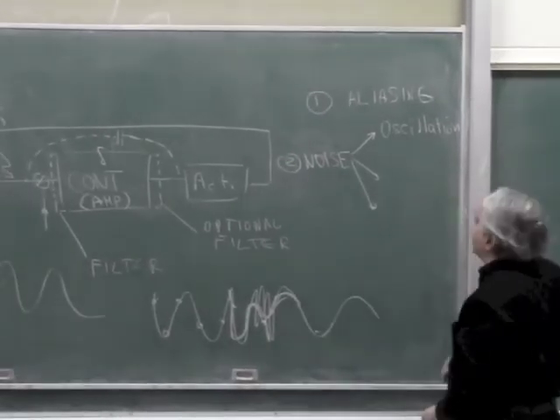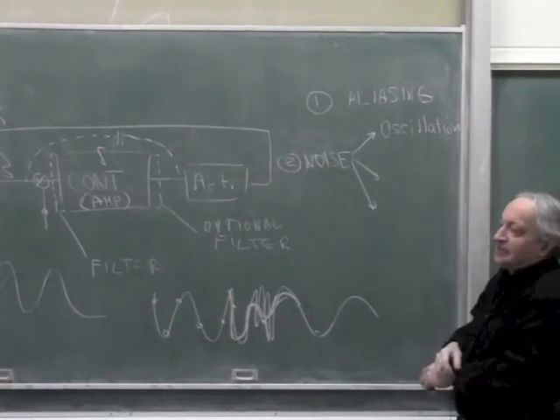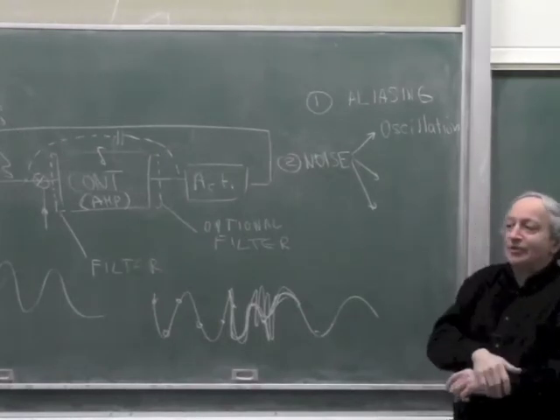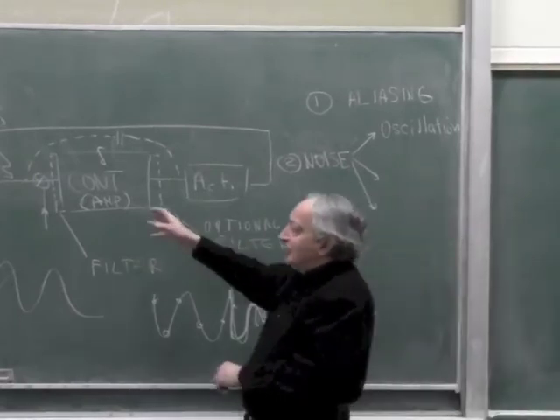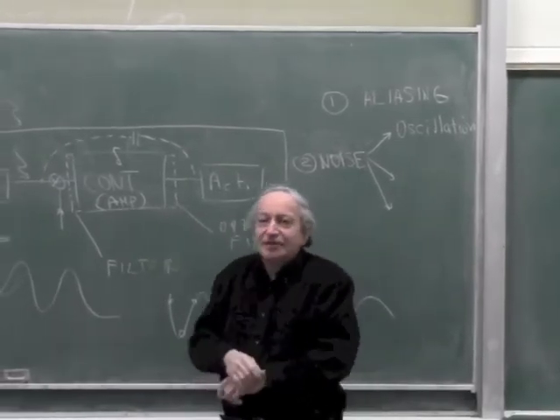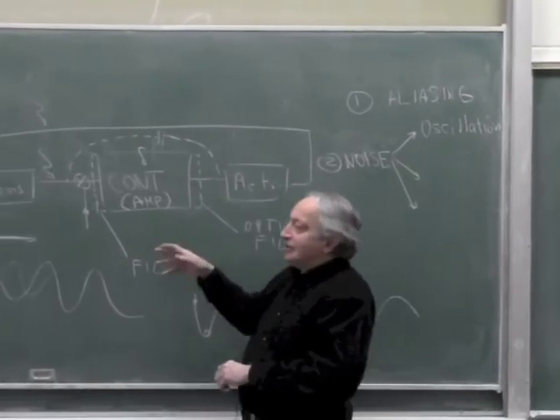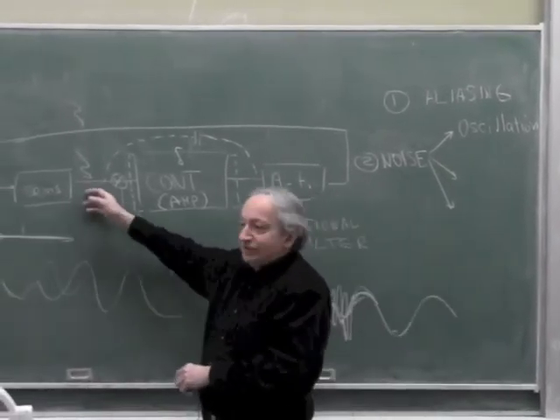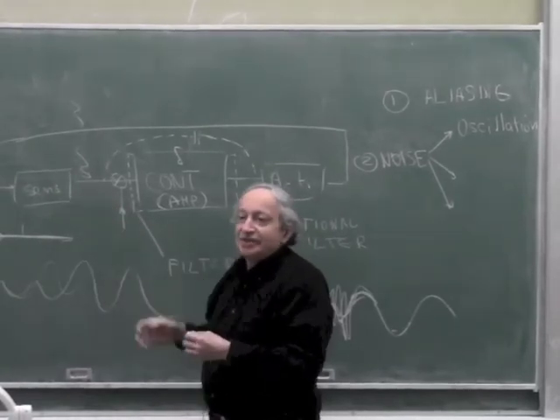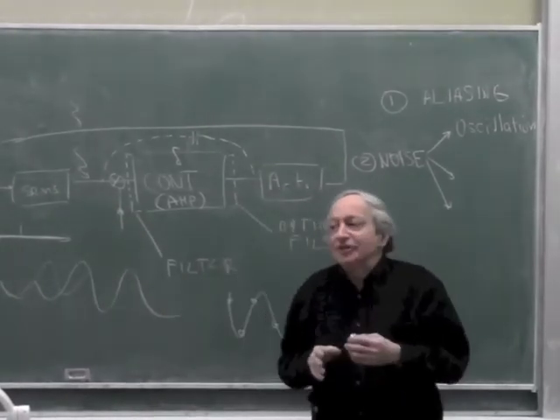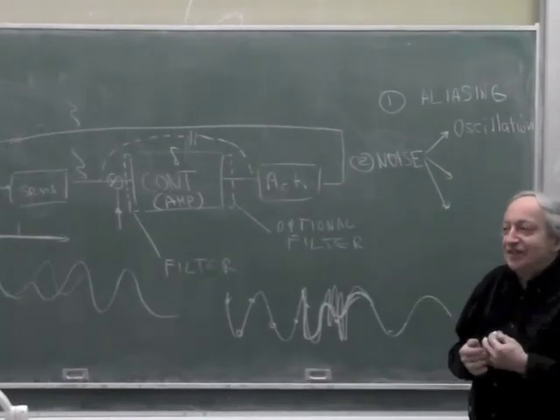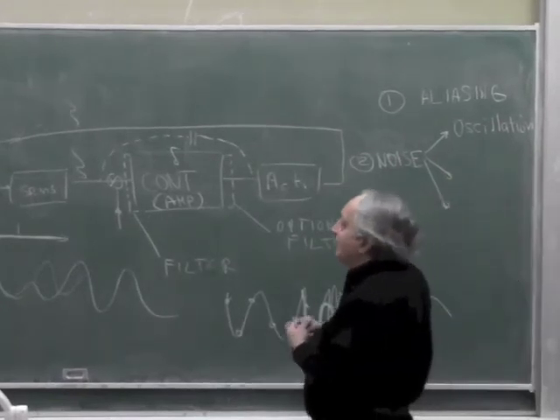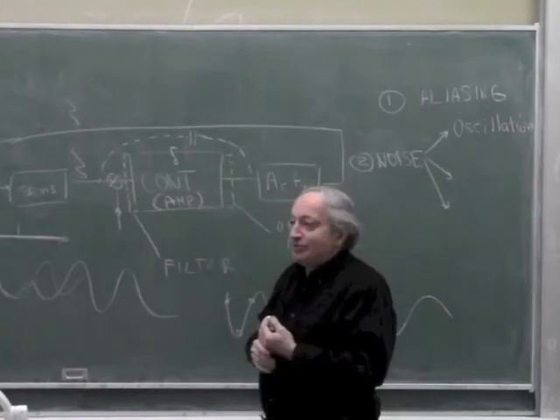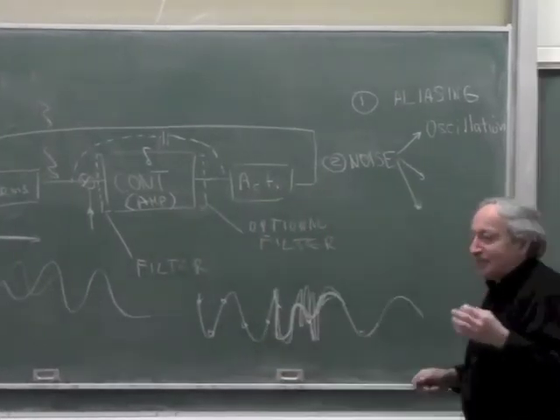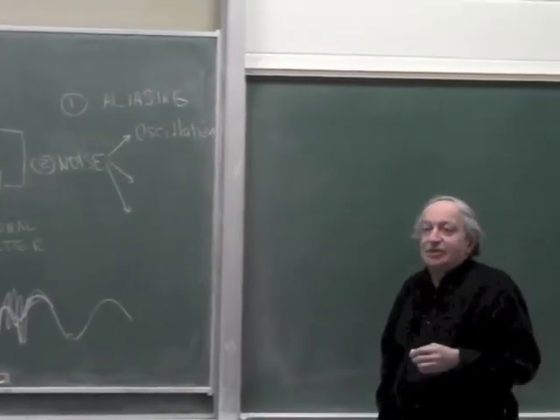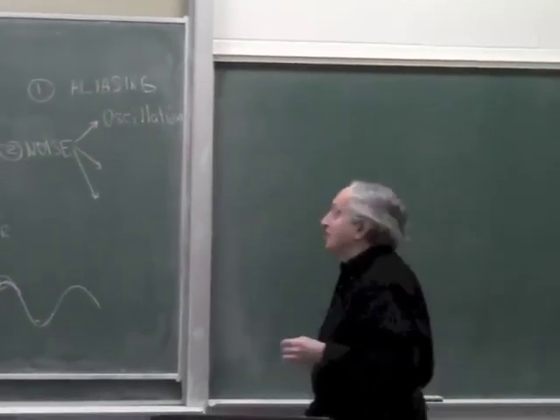Now the second problem that noise causes is actually very surprising, and probably you're not aware of it. Every system has some nonlinearities. So when a high frequency gets together with another frequency—our frequency of interest—in a nonlinear system, it creates new frequencies which didn't exist before. These new frequencies can actually be in the range the actuator can respond to. Let's go over that, because I think this is a concept you're not aware of. That concept is called intermodulation.